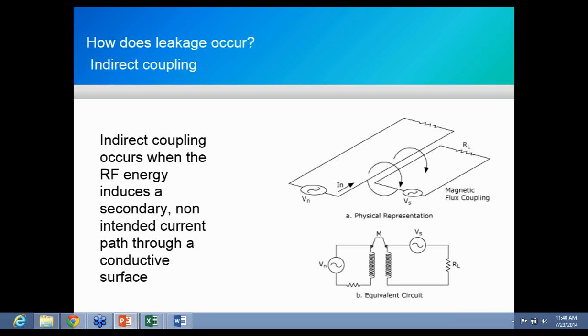Great. So how to test. I used to use the method on the left-hand side. I used a true RMS voltmeter and a current transformer and a large-scale non-inductive 200-watt 1% resistor. But now I use the Unitherm. This diagram shows how really easy it is. In the right-hand image, we're connecting the neutral or dispersive electrode to the ESU analyzer. Those round black things are jumpers, and we're connecting a 200 ohm load to earth ground, just as the regulation tells us to do, while the active electrode is open.